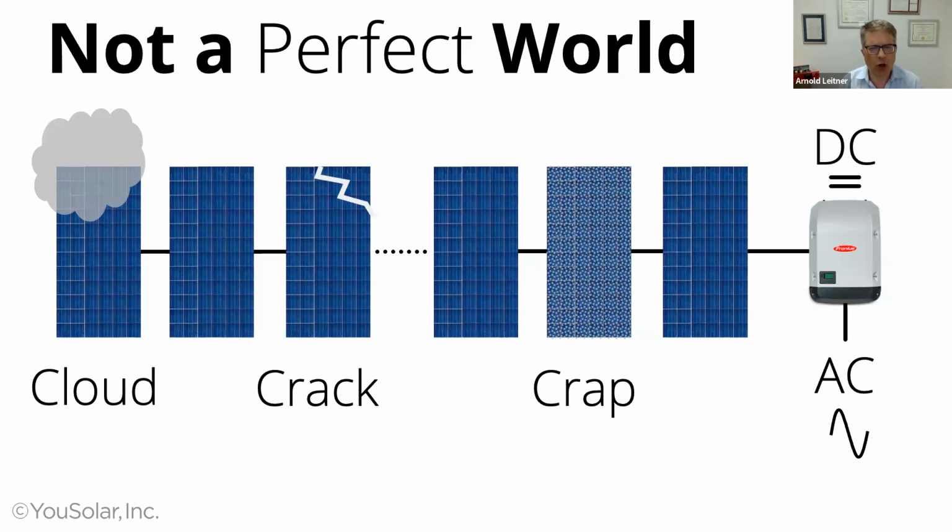So they're pretty much all still operating at 40 volts. But what changes is the amount of current they can deliver for each individual panel. This is a look at each panel, highlighted in yellow. The 9.5 ampere I described earlier for the perfect panel under full sun got reduced for the cloud, which is down half. The cracked panel is only 7 amp maximum. The panel with the dust on it is about 8 amp.